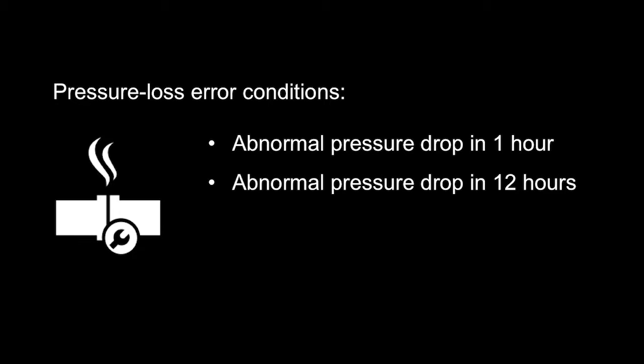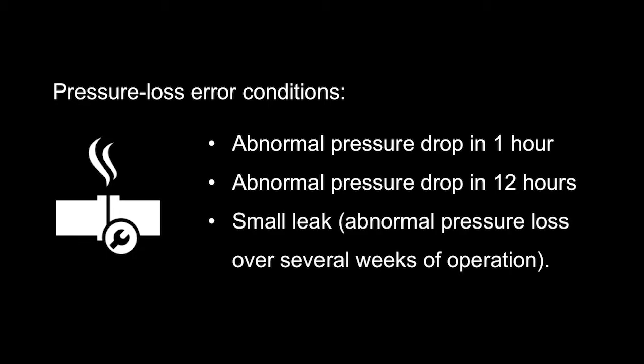Small leaks of calibration gas may be detected by watching for any of the following pressure loss error conditions that are based on readings from the calibration gas pressure sensor. Abnormal pressure drop in 1 hour, abnormal pressure drop in 12 hours, small leak, abnormal pressure loss over several weeks of operation. It is recommended to watch for these errors soon after installing or changing the calibration gas cylinder and to contact Morgan Schaffer for assistance if they appear.